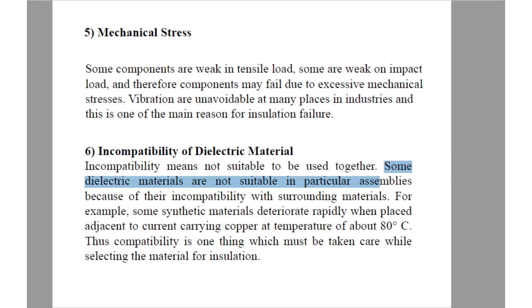The sixth important cause of deterioration is the incompatibility of the dielectric material. Incompatibility means not suitable to be used together. Some dielectric materials are not suitable in particular assemblies because of their incompatibility with the surrounding materials. For example, some synthetic materials deteriorate rapidly when placed adjacent to current carrying copper at a temperature of about 80 degrees Celsius. Thus, compatibility is one thing which must be taken care of while selecting the material of the insulation.